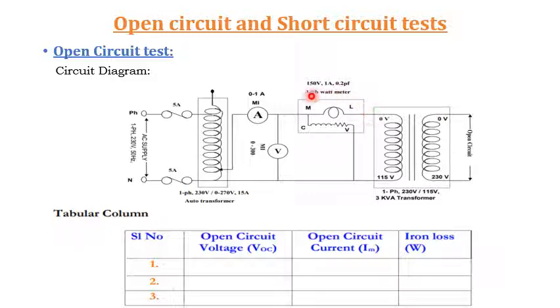A wattmeter is required, a voltmeter is required, an ammeter is required, and even an autotransformer is also required. Now, the rating of the transformer which is under test is single phase 230 volt 115 volt 3 kVA transformer.